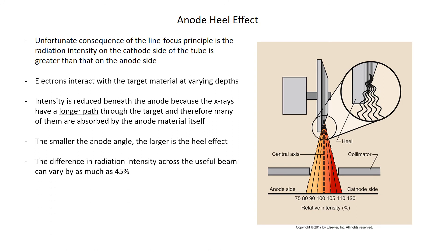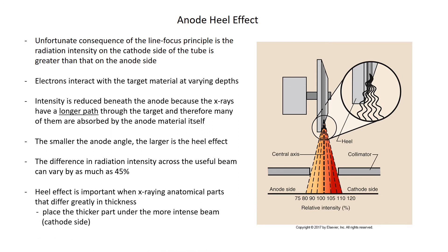The difference in radiation intensity across the useful beam can vary by as much as 45%. On the diagram, 100% would be where the central ray is, with the anode side decreasing rapidly and the cathode side increasing. The heel effect is important when x-raying anatomical parts that differ greatly in thickness. A classic example is the AP of the thoracic spine — the thicker thorax area goes under the cathode side, and the thinner cervicothoracic area goes under the anode side. Place the thicker part under the more intense beam on the cathode side.